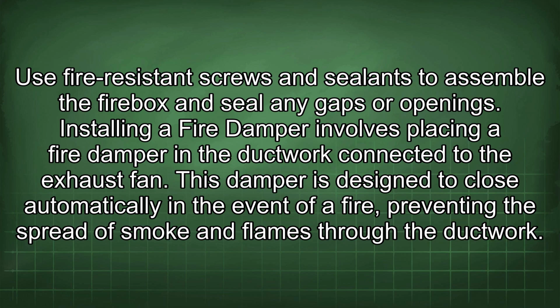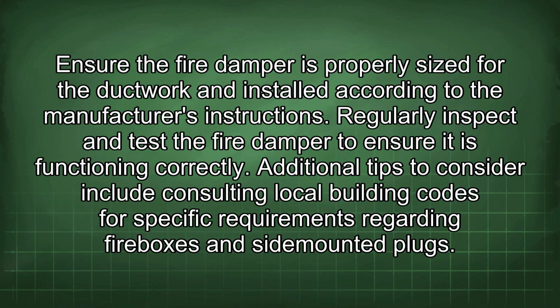Installing a fire damper involves placing a fire damper in the ductwork connected to the exhaust fan. This damper is designed to close automatically in the event of a fire, preventing the spread of smoke and flames through the ductwork. Ensure the fire damper is properly sized for the ductwork and installed according to the manufacturer's instructions. Regularly inspect and test the fire damper to ensure it is functioning correctly.